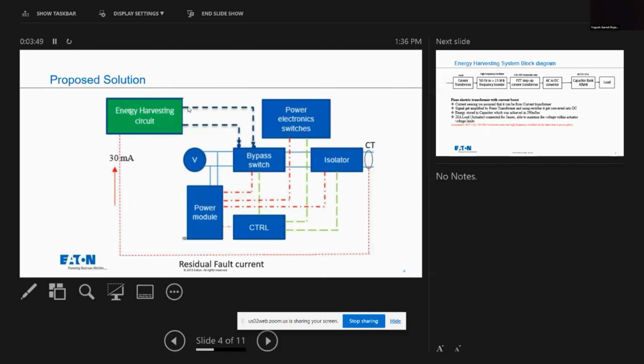Now I will jump to the proposed solution. In this block diagram, we are proposing a solution as I explained in the problem statement. If the grid supply is not available, the time is very short. We have only a limited time, mostly less than 300 millisecond or 250 millisecond, within which we have to turn off that main contact. As you can see, we have an energy harvesting circuit, which will give a signal to this bypass switch. We are getting this signal from the CT, which is 30 milliampere. With this 30 milliampere, using our existing methodology, we give a signal to the bypass switch during this 250 or 300 milliseconds, which will safeguard the human from shock during the fault. So that's our proposal.